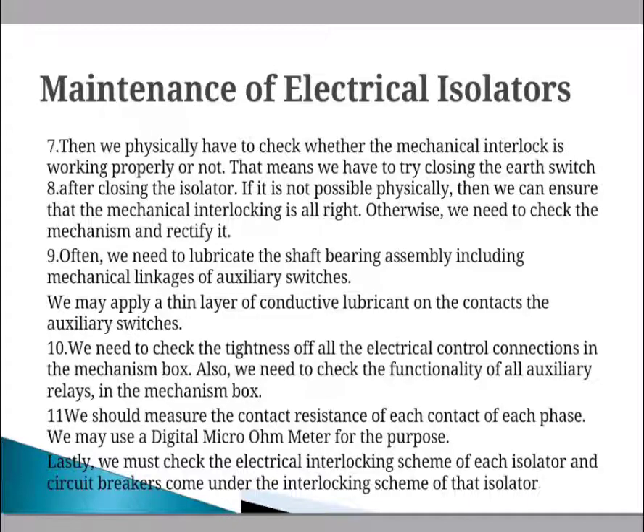Physically check whether the mechanical interlock is working properly — try closing the earthing switch after closing the isolator. If it is not possible physically, then the mechanical interlocking is confirmed as alright; otherwise, check and rectify the mechanism. Lubricate the shaft bearing assembly and apply a thin layer of conductive lubricant on the contacts.